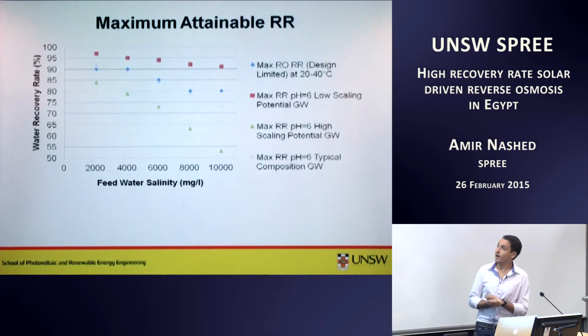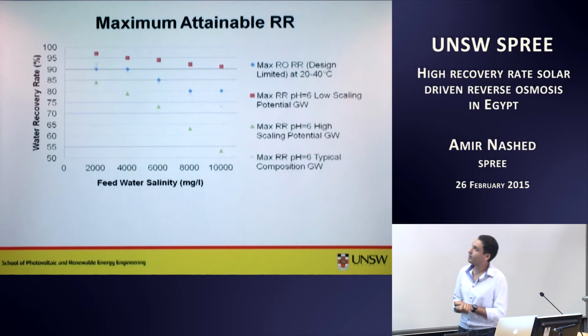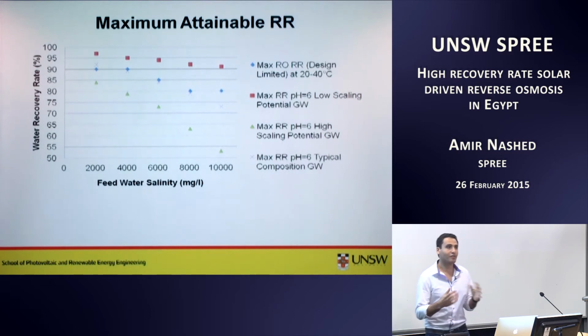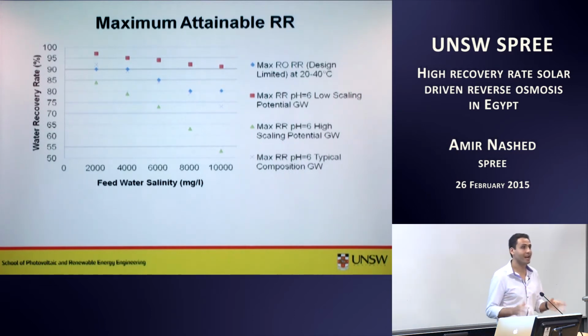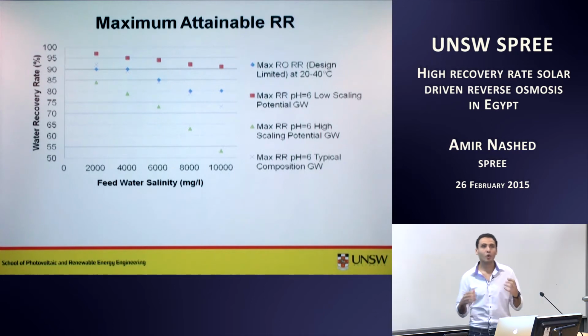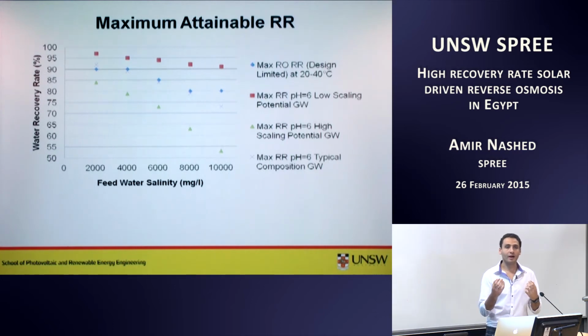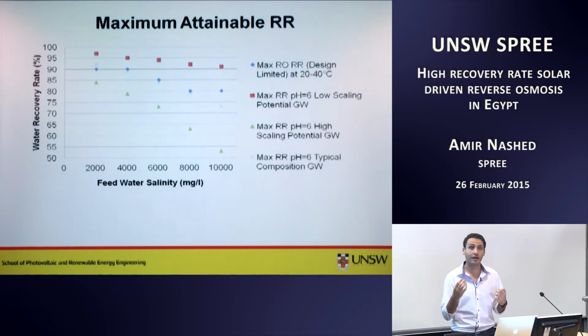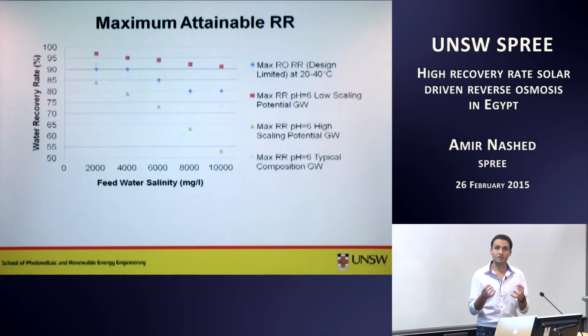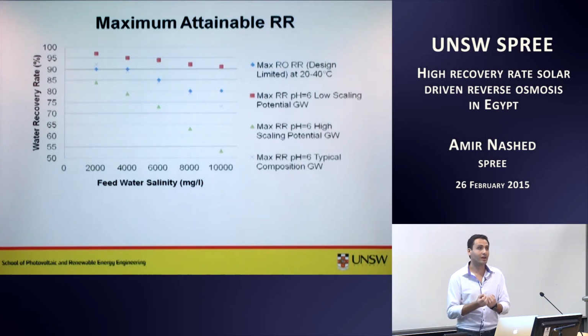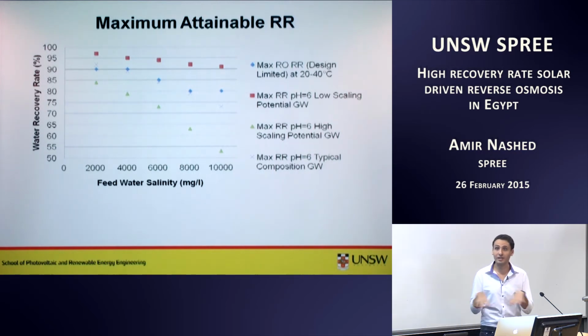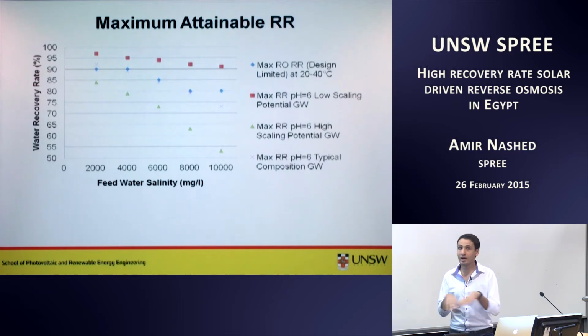So first, let's see the maximum attainable recovery rate. I need to mention here that the recovery rate in general is limited by scaling. What I mean by scaling is that water usually has ions such as calcium, sulfate, and carbonate. At high concentration, they start to precipitate, and when they start to precipitate, they start to clog the membrane. That's why it doesn't function well anymore. So that's your limit. When you start facing scaling, you cannot go beyond; you cannot concentrate the water beyond that.